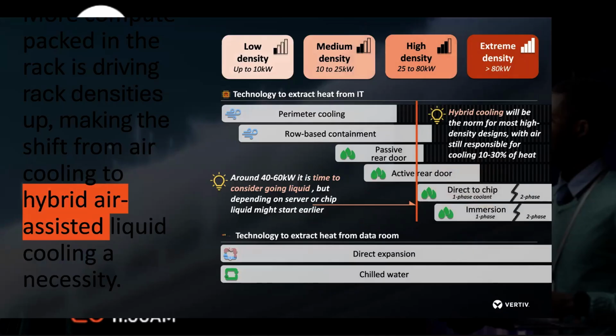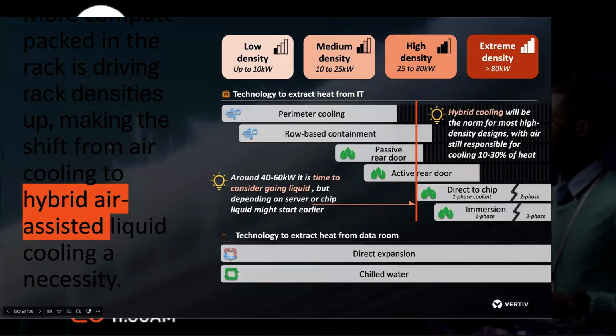Okay, like you can see here: low density up to 10 kilowatts, medium density 10 to 25 kilowatts, high density 25 to 80 kilowatts, and then extreme density, like Okechi mentioned in the slides, from 80 kilowatts up to 200 and even 300 in the coming future is what we'll be expecting from our servers.